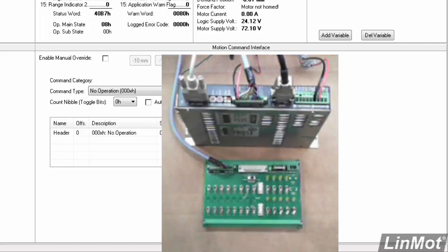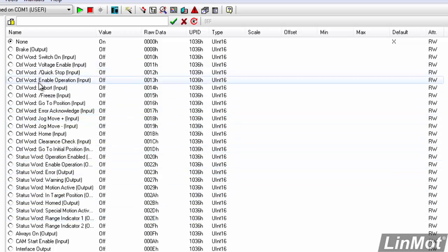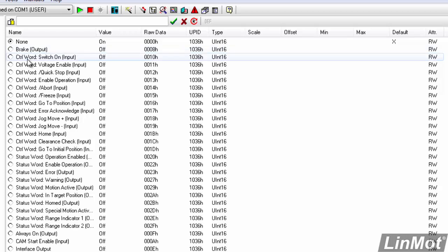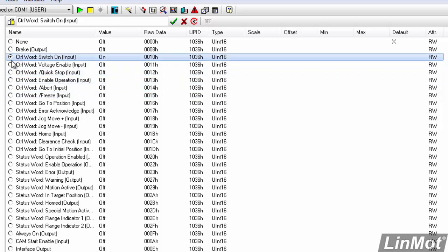So, the first one we'll do is the X4 connector pin 3. When we click on that, we'll have all these choices of functions that we can connect up to pin 3. What we're going to do for the first one is connect that to the control word switch-on bit. To do that, we double-click on the dot. Up comes the dialog box warning us that the firmware on the drive is running and must be stopped before parameters can be written. Do you want to stop it now? Yes. So, we stop the firmware, and now pin 3 is connected to the function control word switch-on.